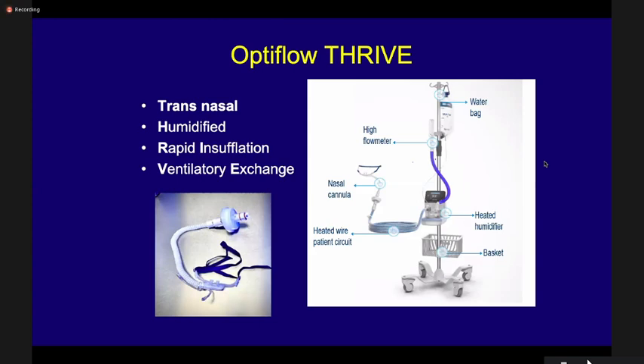Another device which has been added to our armamentarium recently is OptiFlow Thrive. Thrive stands for transnasal humidified rapid insufflation ventilatory exchange. This device consists of a water bag, a high flow meter, a heated humidifier, a heated wire patient circuit, and a nasal cannula, as you see on the left side, which is a very soft silicon catheter.